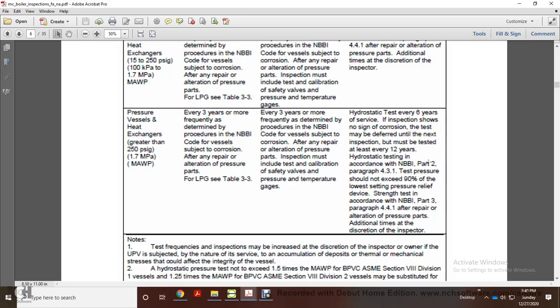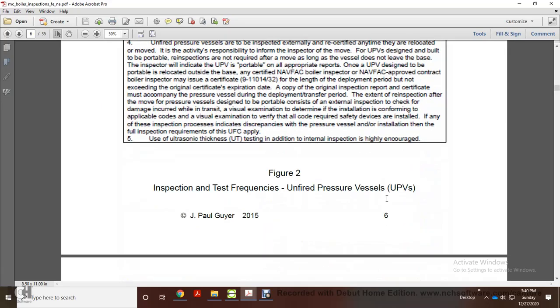Hydrostatic testing per NBBI Part 2, paragraph 431, test pressure should not exceed 90% of the lowest setting of the pressure relief device. Strength testing according to NBBI Part 3, paragraph 441, after repair or alteration of pressure parts, and at additional times at the discretion of the inspector.